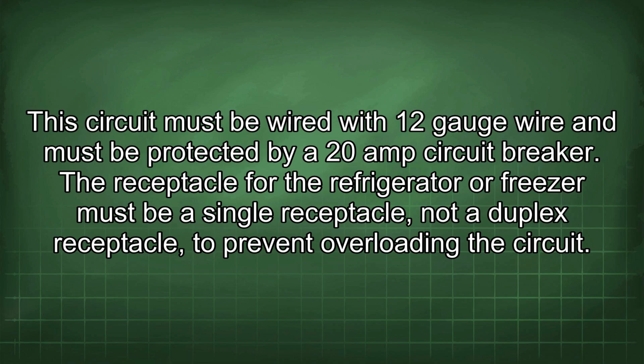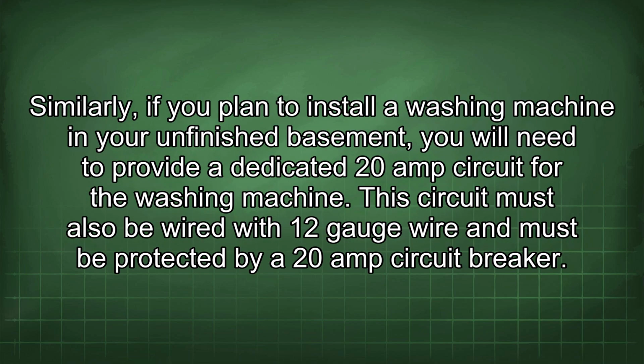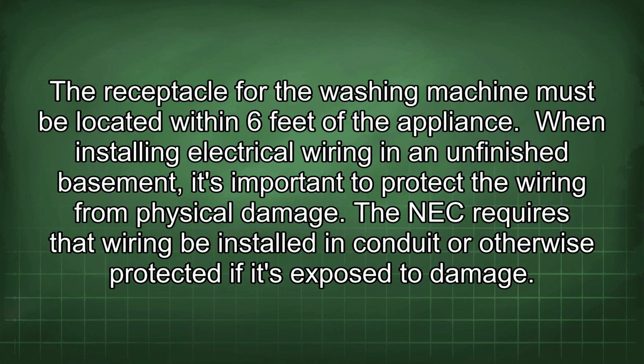The receptacle for the refrigerator or freezer must be a single receptacle, not a duplex receptacle, to prevent overloading the circuit. Similarly, if you plan to install a washing machine in your unfinished basement, you will need to provide a dedicated 20-amp circuit for the washing machine. This circuit must also be wired with 12-gauge wire and must be protected by a 20-amp circuit breaker. The receptacle for the washing machine must be located within 6 feet of the appliance.